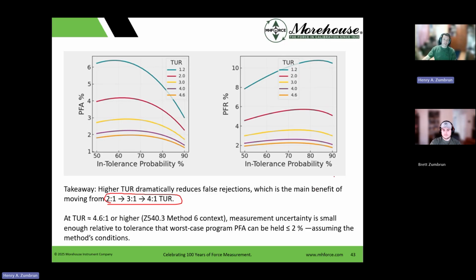But then Paul Reese and John Harbin did this awesome paper where they ran all these samples and calculations using Method 6, and at 4.6 to 1 or higher in a Method 6 context, measurement uncertainty is small enough relative to tolerance that the PFA, the probability of false accept, is held to less than 2%, assuming the method's conditions.